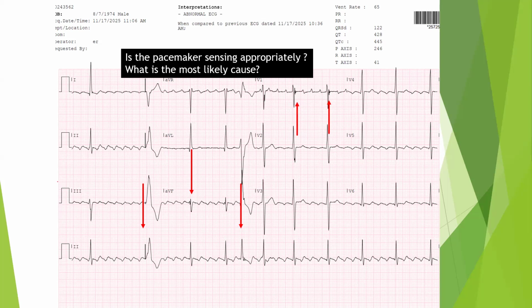So normally, most of the time with such a type of failure of sensing, you try to see if you can program around it. Normally for any lead malfunction, don't rush to replace the lead. Always try to see if there is a programmable alternative for the patient.